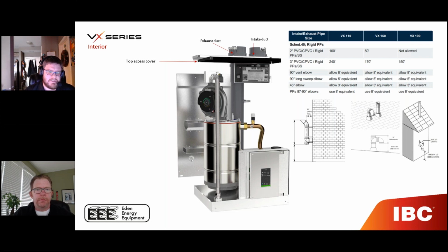One thing unique to our venting is this plastic vent duct, changed from our previous stainless steel. We now have a full polypropylene assembly in that venting assembly, with a nice big test port that came with that polypropylene adapter. We got a lot of feedback from customers that the flue gas analyzers they were using have a much fatter probe, the more commercial style ones have a bigger probe, so there's now a bigger plug there. It even comes with an adapter if you want to measure pressure at that location, like a little nozzle adapter.